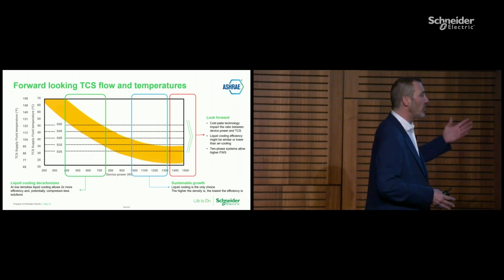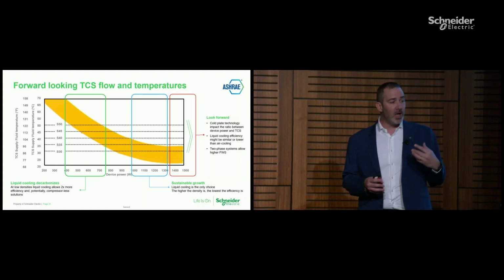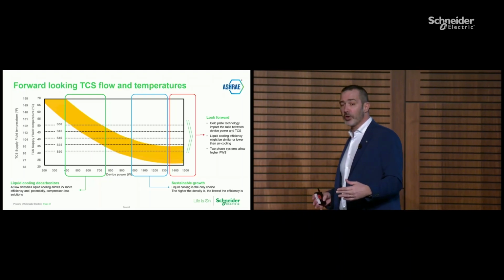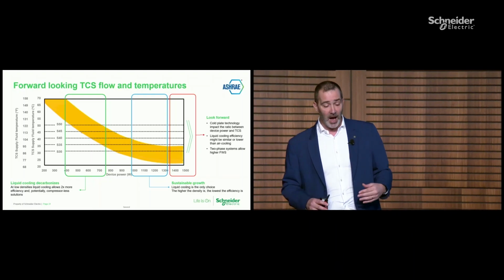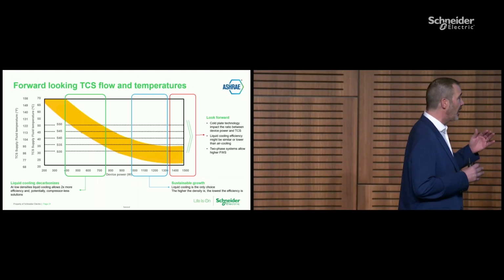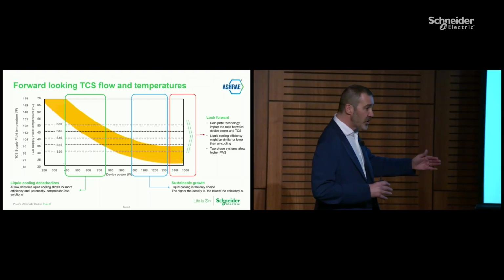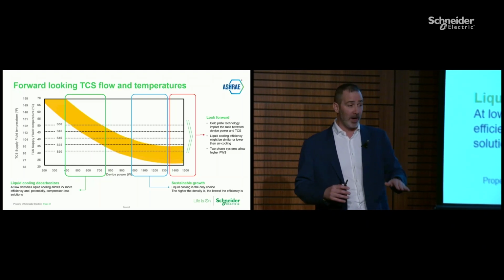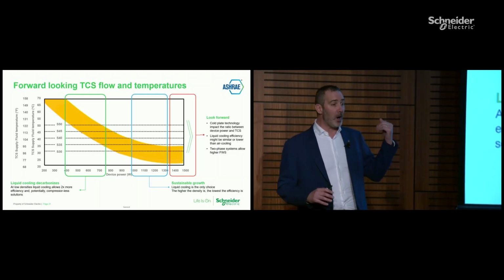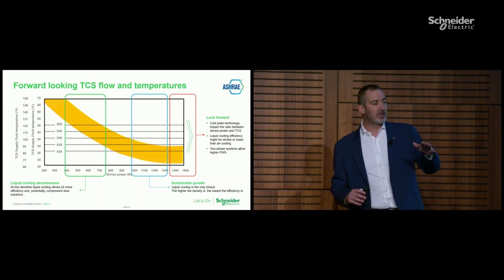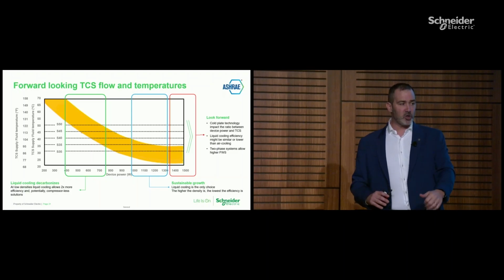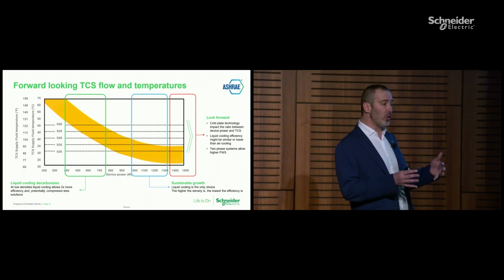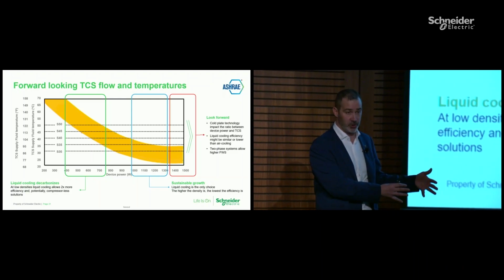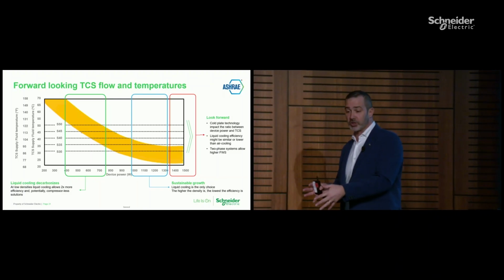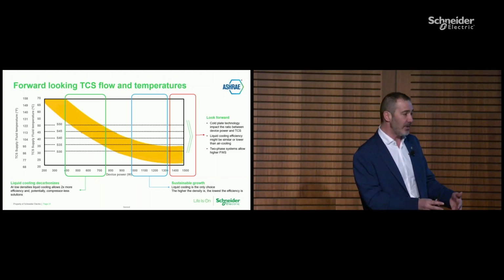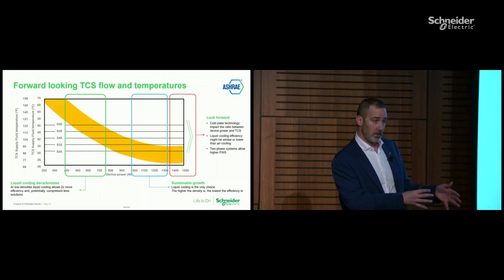The big question is, what else? Are we still going to reduce the water temperature? Or should I now consider the minimum water temperature at 30, having added 25 and 20, and discussed 2 weeks ago about 15 and 10? This means having a chiller outdoor rated to provide water at 7 degrees Celsius, which was the usual temperature in data centers 20 years ago.